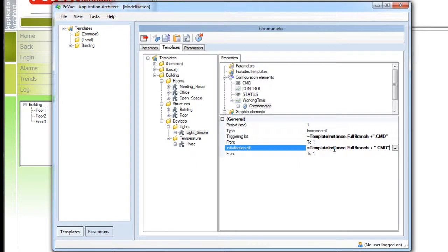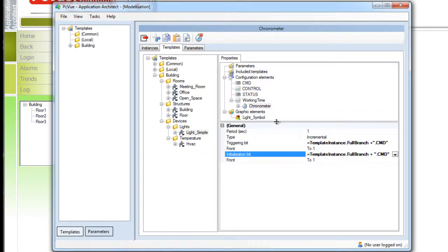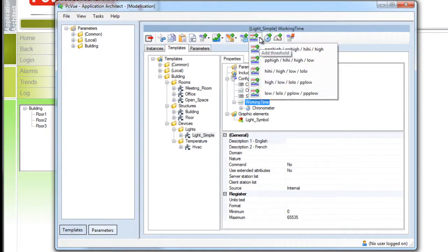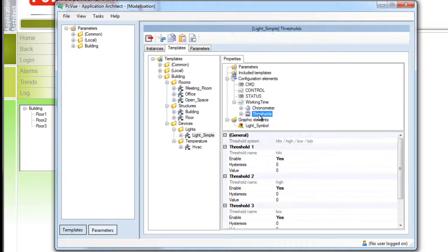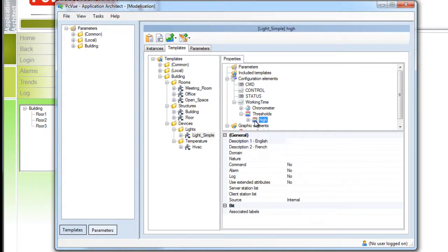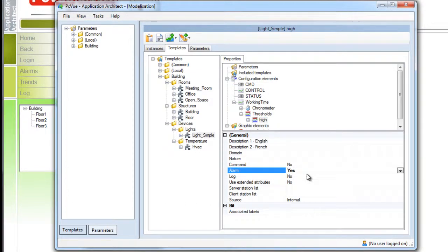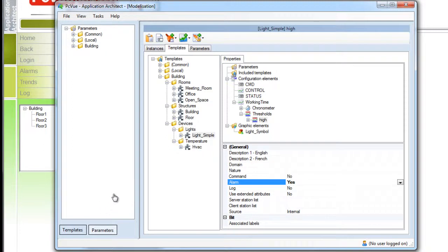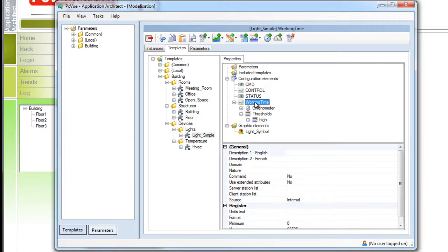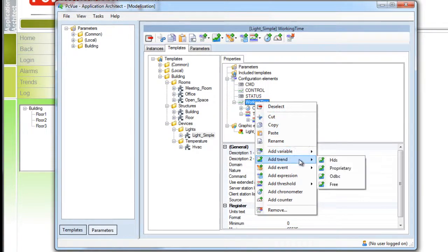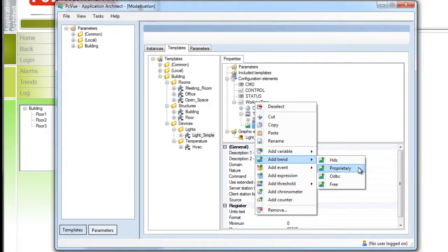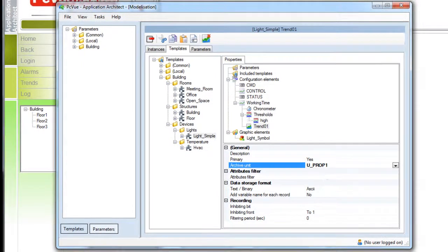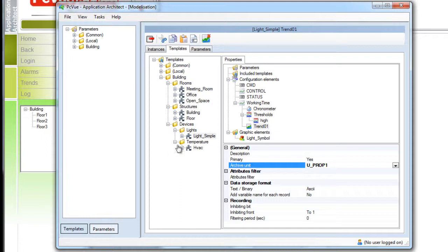The chronometer is now ready and the last step is to define a threshold to trigger an alarm. We add a threshold system to our working time variable and we can activate a high threshold with a value of 10 as shown. The associated variable must be defined as an alarm and the customer also needs to record the time of use for the light. If you right click on the variable working time you can add the variable as a trend to be archived in a proprietary format in an existing archive unit. And that's it. Our model light now is ready.